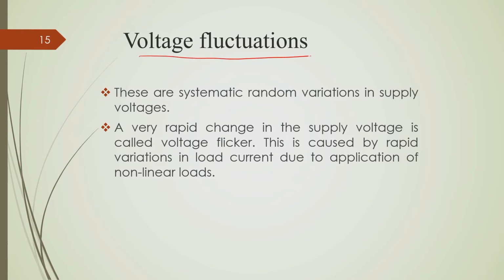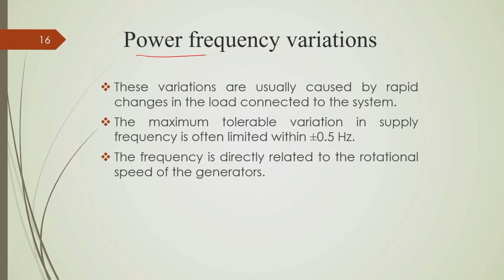Okay. Now, there is another type of power quality problem which is called voltage fluctuation, or we call this a voltage flicker. It is a rapid change in the supply voltage, which causes some eye sensation, and this is basically caused by rapid variation in load current due to application of nonlinear loads. Okay. There is another kind of voltage quality problem, which is called power frequency variation. We intend to have a constant frequency, as I said, that is 50 hertz, but we never get it. So, there is some tolerable variation of supply frequency. Often this varies from country to country, but anything plus minus 0.5 hertz is somewhat acceptable, and it also depends upon different factors. But if the frequency lies within this acceptable band, we do not have any problem.